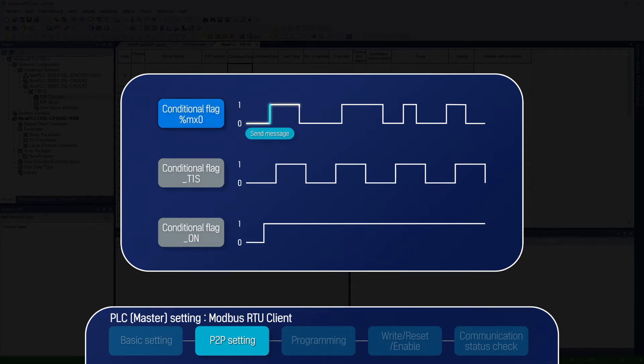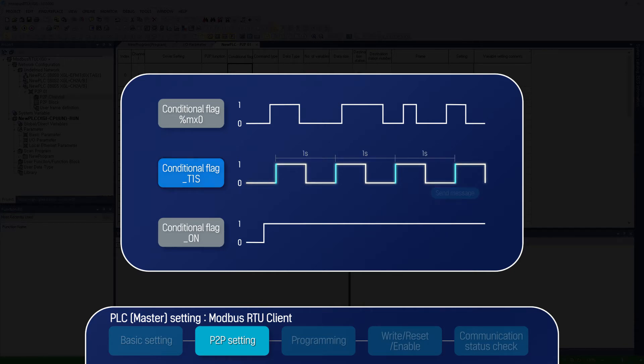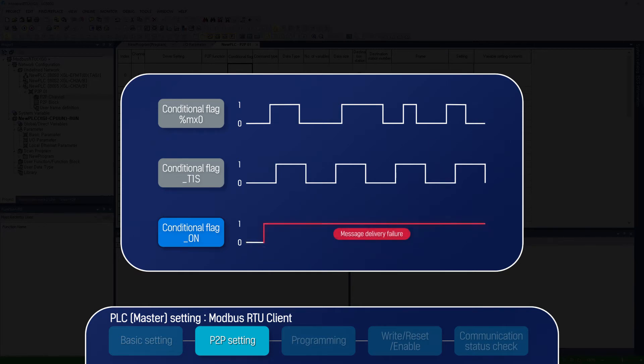We will put MX0 in conditional flag. The index 0 message will be sent when MX0 bit turns on in PLC program. Counter, communication flag, or bit shift commands are generally used as a conditional flag. You could also choose a system flag for a conditional flag. FX147 device in XGI is used for the 1 second basis clock. If FX147 bit 1 second flag device in XGI is applied as the conditional flag, its communication message will be transmitted every second. Note that always-on bit device FX153 in XGI is not a proper conditional flag, as it is always on and does not change from 0 to 1.